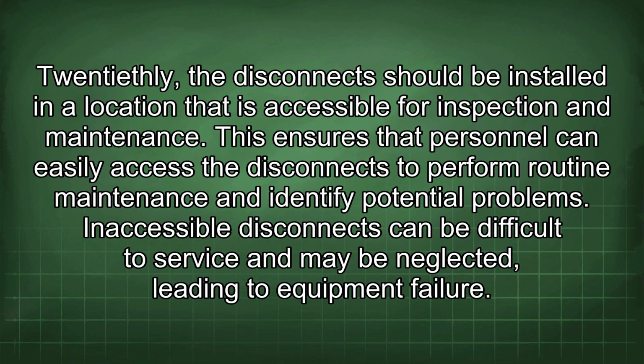20thly, the disconnect should be installed in a location that is accessible for inspection and maintenance. This ensures that personnel can easily access the disconnects to perform routine maintenance and identify potential problems. Inaccessible disconnects can be difficult to service and may be neglected, leading to equipment failure.